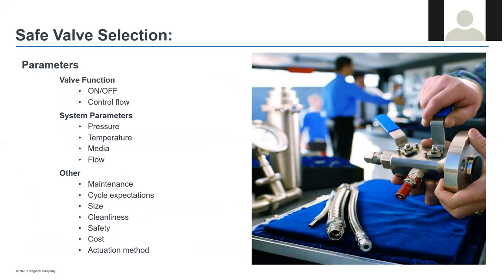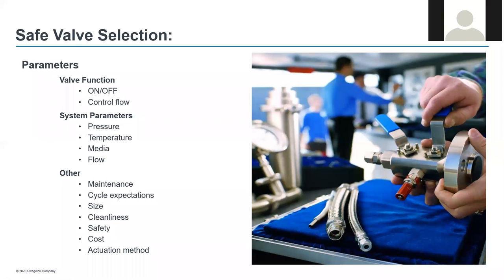A little bit about safe valve selection. Some of the parameters we look at when helping customers select a valve: first is valve function — is this going to be an on-off valve to start and stop flow, or are you looking to control flow? A ball valve is for on-off, and a needle valve is more of a control valve for regulating flow. System parameters include pressure, temperature, media type, and flow. We also consider maintenance, cycle expectations, valve size, cleanliness, safety, cost, and actuation methods — we can offer manual, pneumatic, and electric actuation.